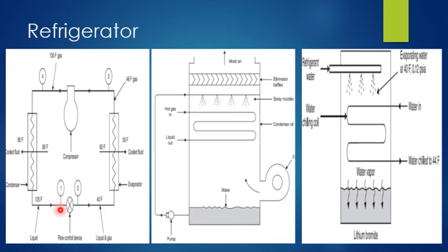Process 4 to 1: the refrigerant leaves the compressor as a gas at high temperature and high pressure. In order to change it to a liquid, heat must be removed from it, and this is accomplished in a heat exchanger called the condenser. The refrigerant flows through one circuit in the condenser, while in the other circuit a cooling fluid flows at a temperature lower than that of the refrigerant. Heat therefore transfers from the refrigerant to the cooling fluid, and as a result the refrigerant condenses to a liquid, as shown in this figure.